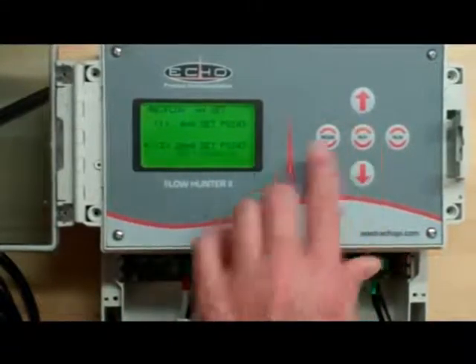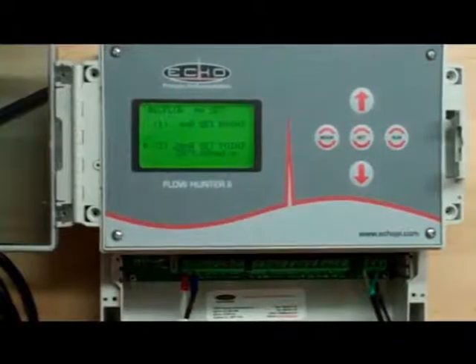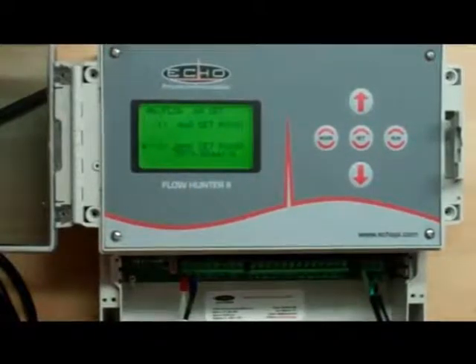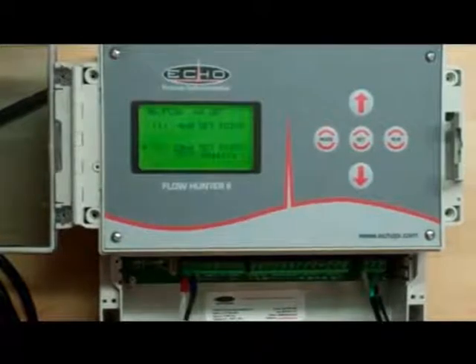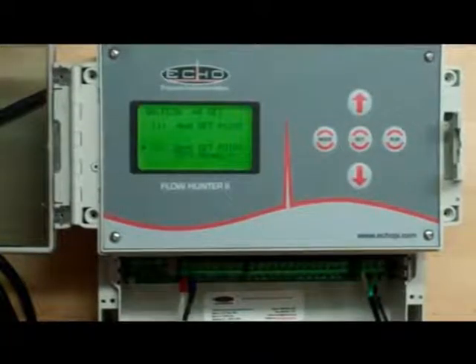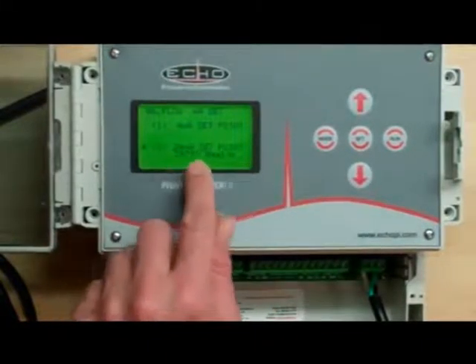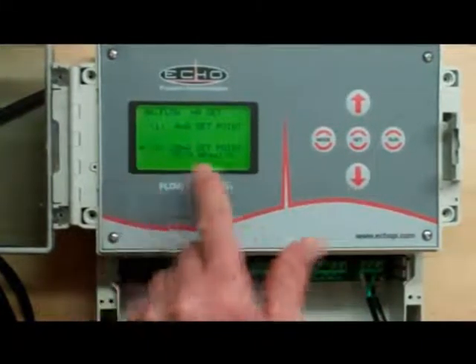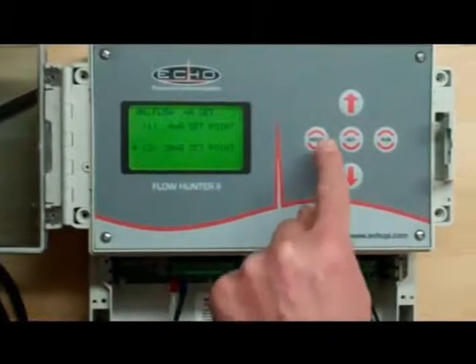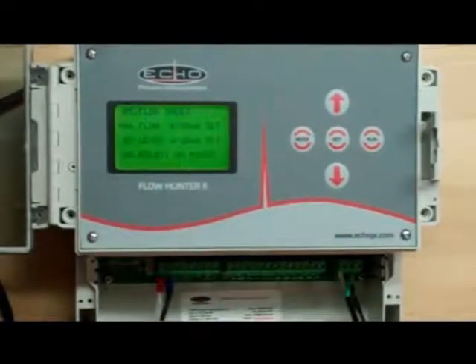Now we're going to move down to the 20 milliamp set point. We're going to hit set for the number to come up. What we have is our 9-inch Parshall flume. We're going to do a 2-foot max head, and at 2 feet, that is 3979 gallons per minute. We're going to hit set to save. Hit mode to go back to the main menu.